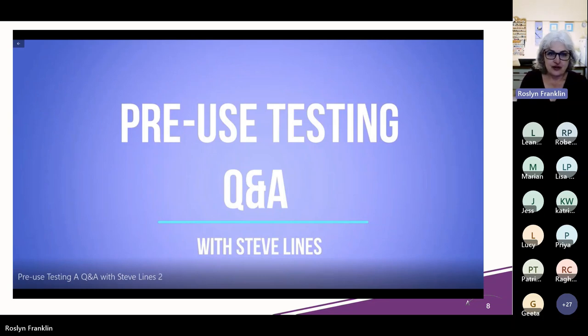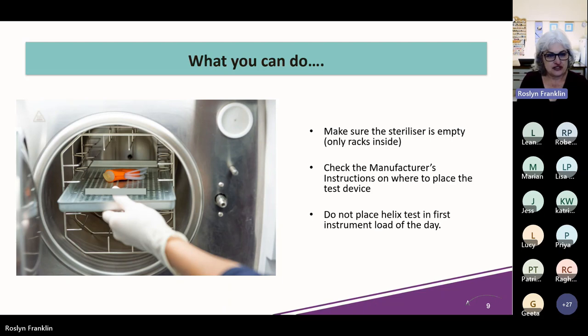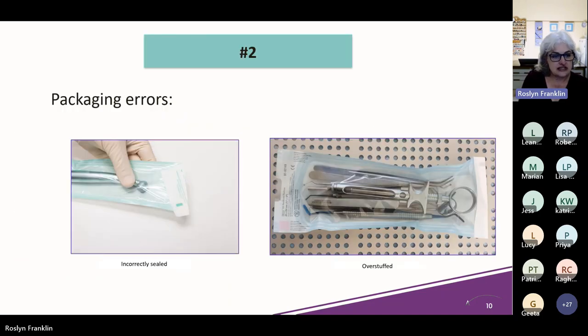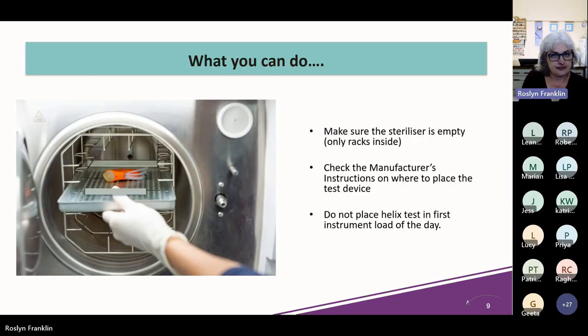So what you want to do is make sure the sterilizer is empty, with only the racks inside when you put your Helix test in there. Most of you will just be running the Helix test because you'll be popping your handpieces in there. The Bowie-Dick test is a piece of cardboard with a colored pattern on top, designed for loads of things inside that are just porous, like drapes and gauzes. So you'll find that your Helix test is much more challenging.